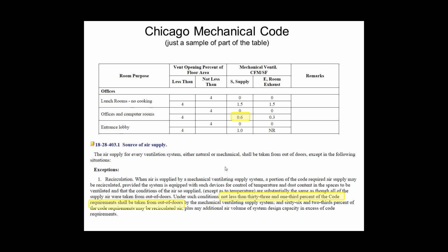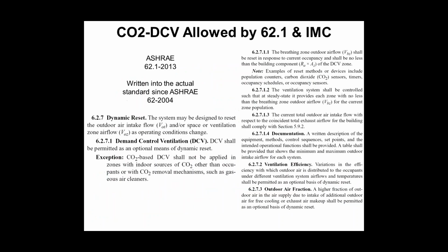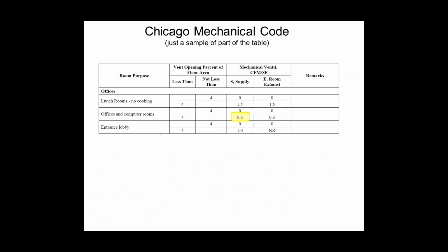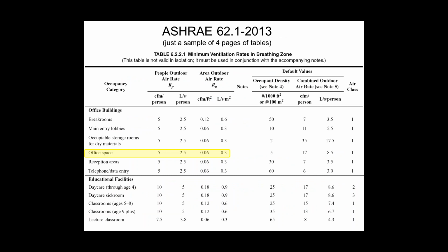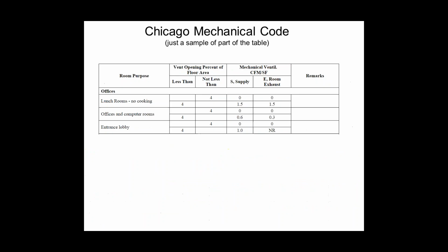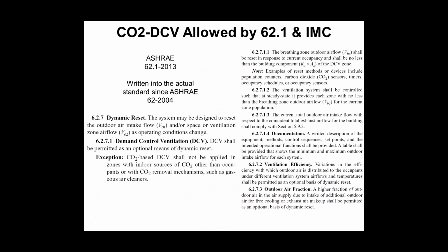The mechanical designer should be dictating to the controls designer how much outside air he needs to bring in, and the controls person will then take that and decide how much he can modulate. So you need to understand how this table works to know which part you can modulate. You can modulate the 5 CFM per person part. You cannot modulate the 0.06 CFM per square foot part.